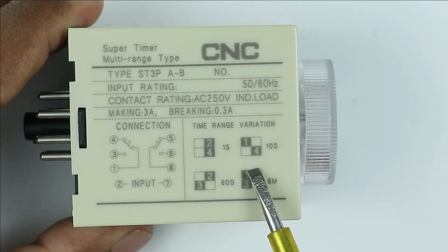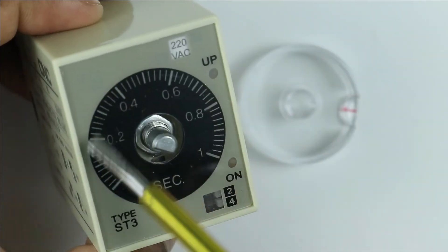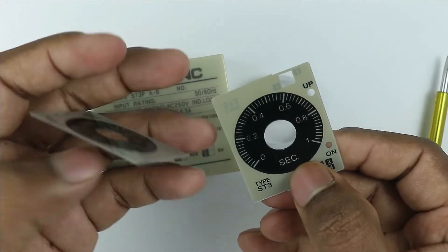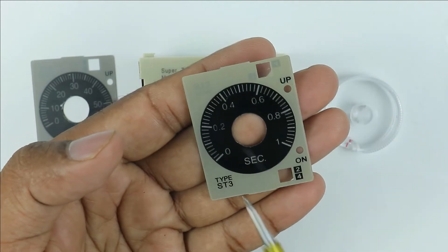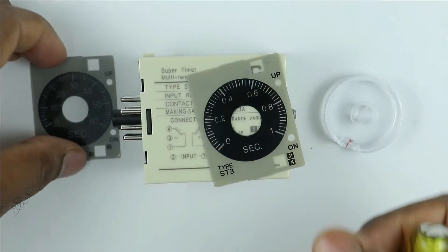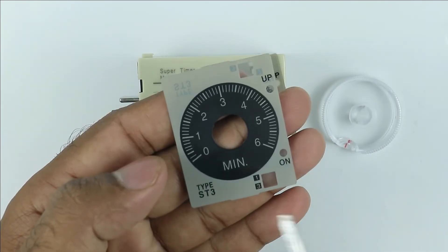To select the time range for programming, you have to open this cover. After this, remove this plate. You can see two different plates are provided, and in both plates there are two different time ranges. In the first plate, the time range is 0 to 1 second; in the second plate, time range is 0 to 10 seconds. The third plate range is 0 to 60 seconds, and in the last plate, range is 0 to 6 minutes.